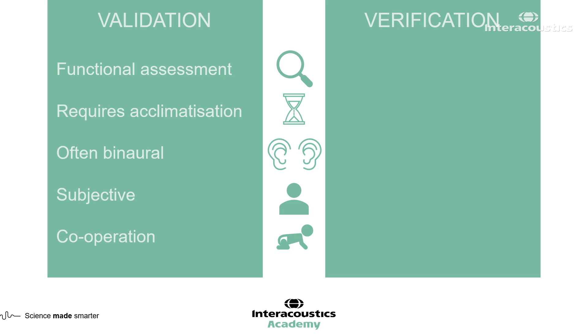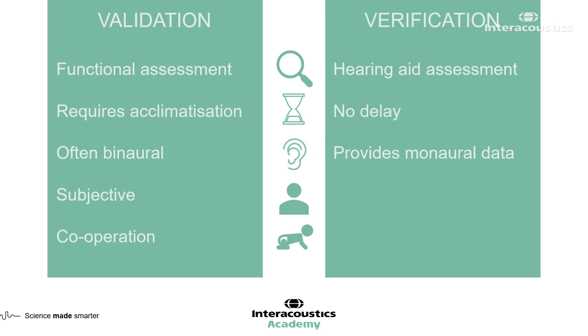These measures usually require some element of cooperation — even corticals, which are ideal for an infant population who aren't able to take part in more active speech testing. On the other hand, our verification process is really looking at whether the hearing aid is producing the desired output. This is where real ear measurements play a part. There's no delay and no requirement for acclimatization, so we can perform verification at the time of fitting or upgrading a hearing aid or changing settings. It provides us with monaural data — information about each individual hearing aid we are assessing.